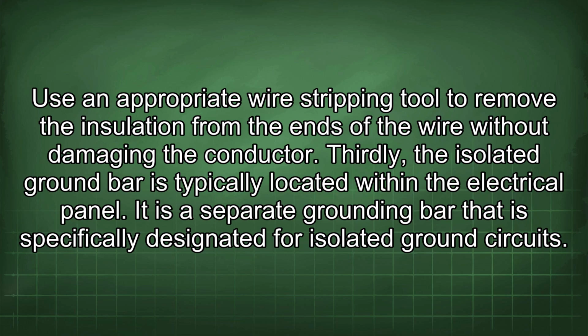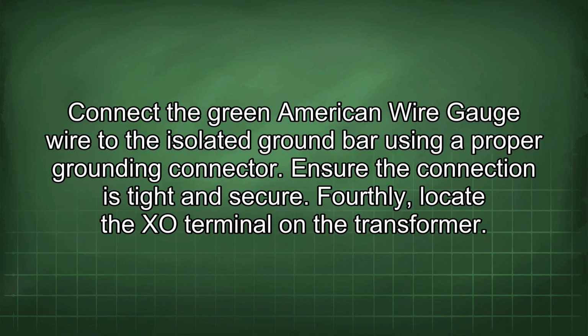Thirdly, the isolated ground bar is typically located within the electrical panel. It is a separate grounding bar that is specifically designated for isolated ground circuits. Connect the green American wire gauge wire to the isolated ground bar using a proper grounding connector. Ensure the connection is tight and secure.